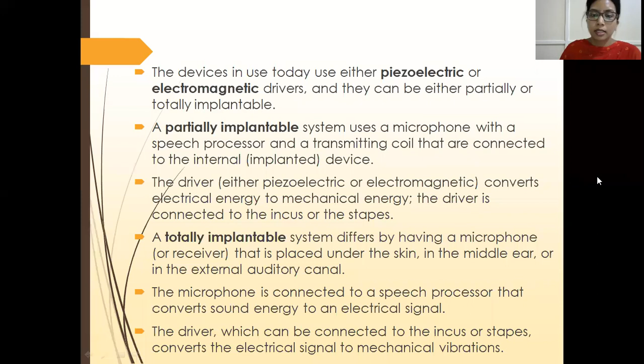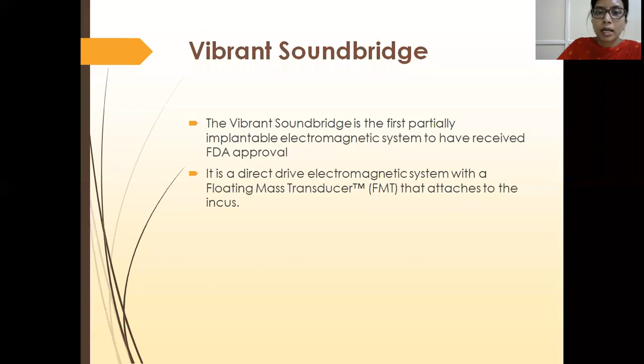Again, your Vibrant Soundbridge also happens to be a question. So this Vibrant Soundbridge is the first partially implantable electromagnetic system to have received an FDA approval. It is a direct drive of electromagnetic type, and it has a floating mass transducer that is attached to the incus. Middle ear implantable devices means literally a part is implanted in the middle ear. So this FMT device is attached to your incus.